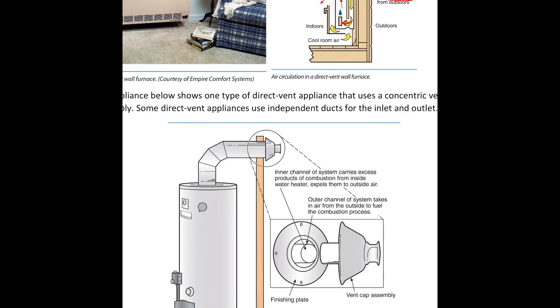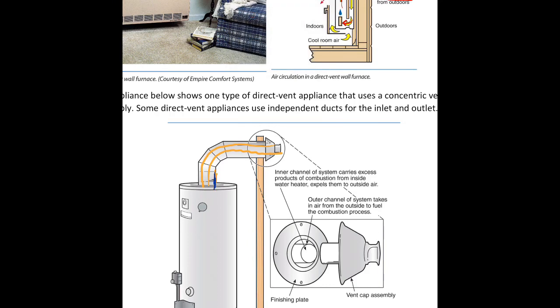The key on these is to have these connected correctly. This has to be connected here and here. It's got to be connected to the outlet - the outer pipe has to be connected to allow the pressure plane. Whatever pressure, whether it's a wind blowing this way, the exhaust is seeing the same pressure as the intake air and that has to be the case.